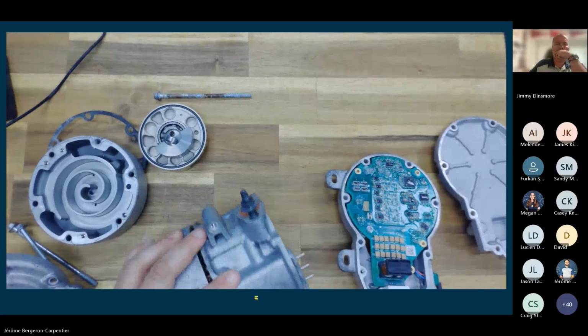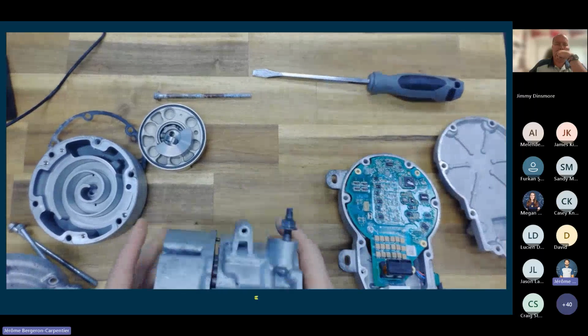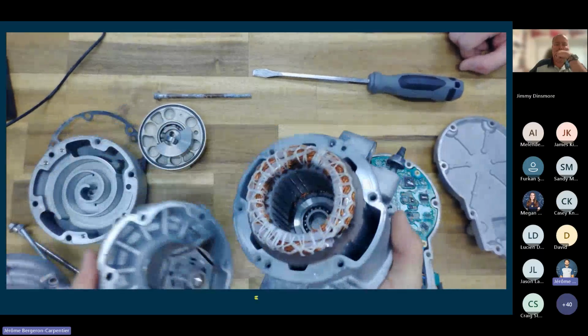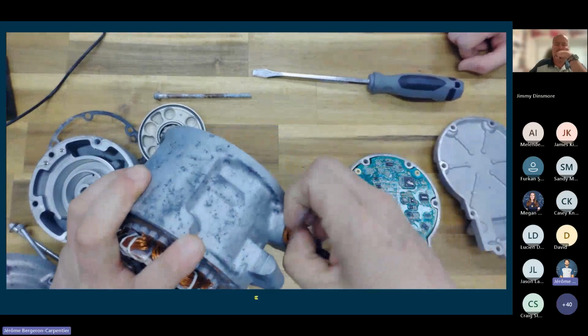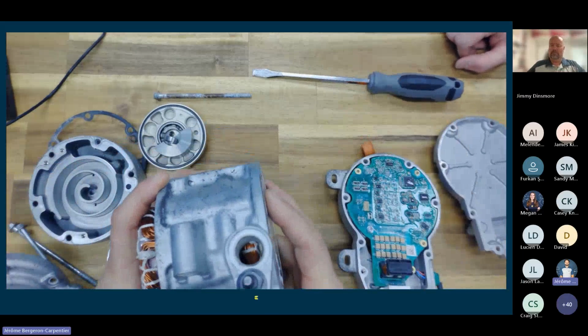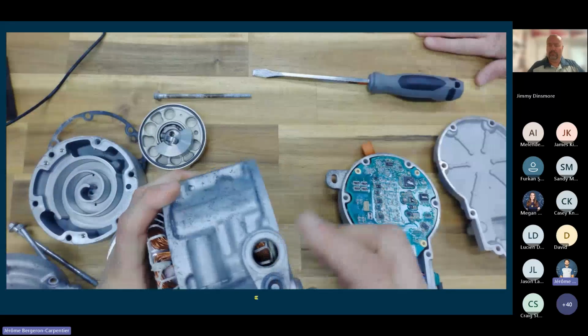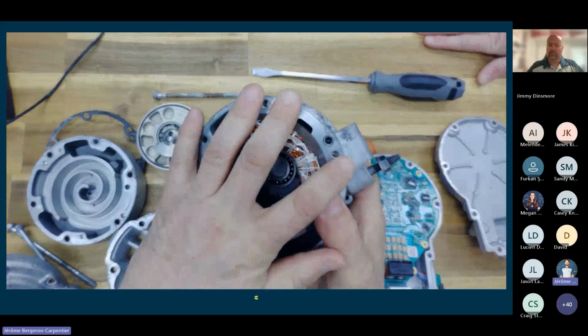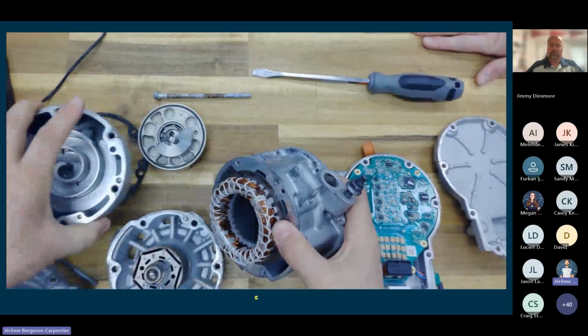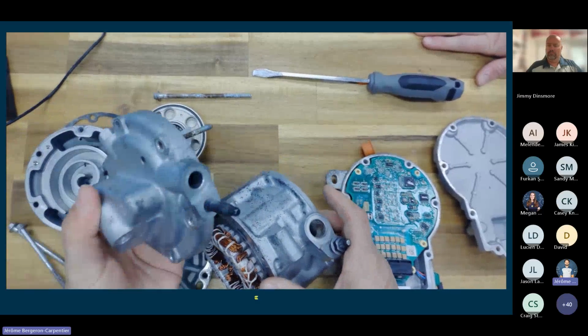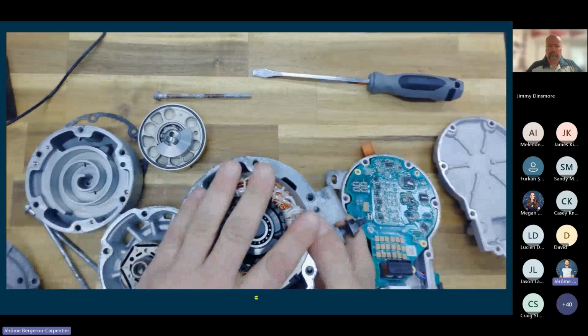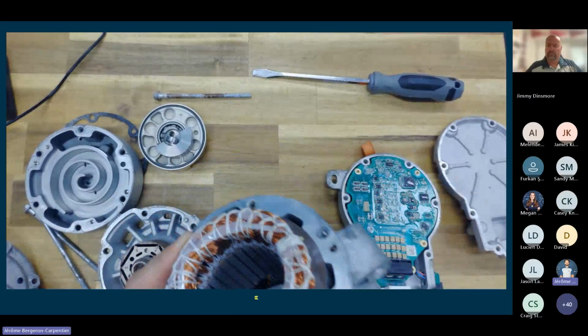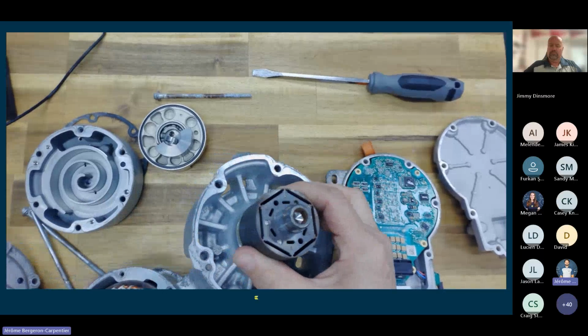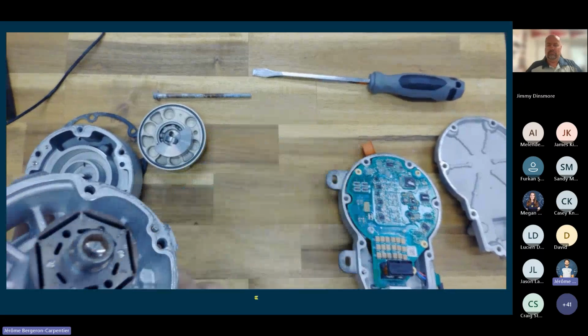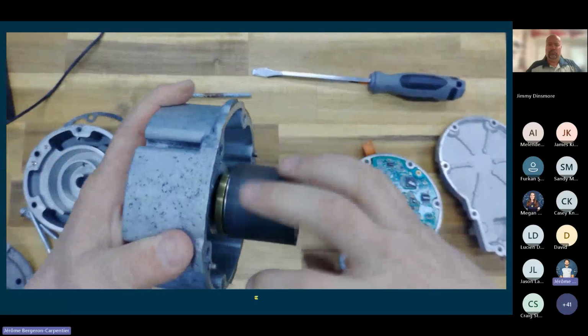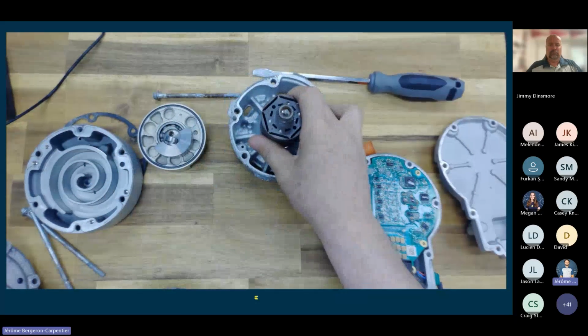Here we go. Okay. So now as I pull this apart, this is the thing that surprises most people: the actual intake port on this compressor is directly exposed to the stator itself. So the windings are actually exposed to the refrigerant and oil that goes through the compressor, through the scroll, to be discharged out the back of the compressor as high pressure gas. So this one here, the scroll itself is attached directly to a rotor, and here's our rotor here. In fact, this compressor doesn't have an insulation fault, as we described earlier, but actually has a bearing fault in it. That's why it was replaced, but it gives a great example of it.